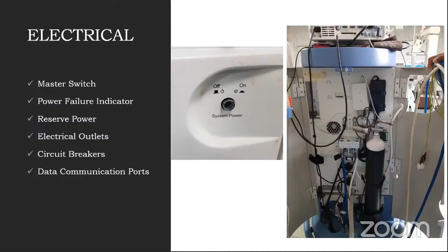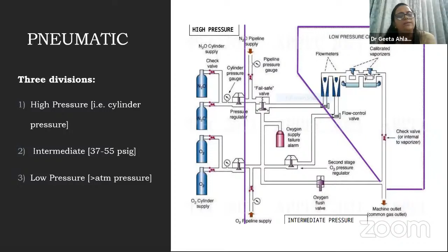Coming to the pneumatic part, however high-tech the machine may be, the basic design remains the same. It has three basic divisions: the high pressure system, the intermediate pressure system, and the low pressure system. Talking of the high pressure system first, we have the yoke assembly and yoke hangers, where the cylinder is attached, because the machine started basically on the cylinder. Now we have pipeline facilities, but still we depend on cylinders for our backup.